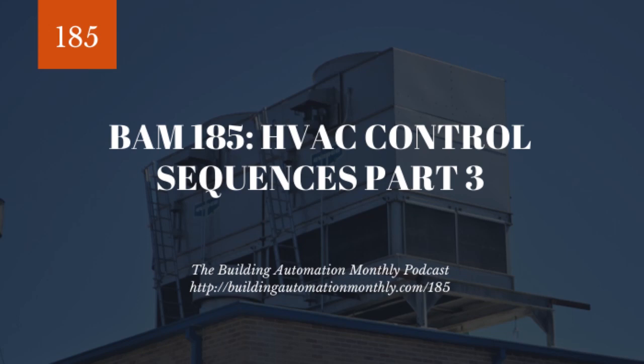It's not something I particularly like because it makes it difficult to troubleshoot. And honestly, I've seen more folks mess it up than get it right. I think most folks would be better just picking a static discharge air pressure set point, especially here in the US where utility costs are so low. I know that not doing a reset sequence slightly increases the wear and tear on the equipment and increases the utility cost of the equipment. But here in the US, we can afford that. Overseas, maybe not so much. But I will tell you, I've seen more problems with reset sequences than I have seen with static discharge air pressure set points.